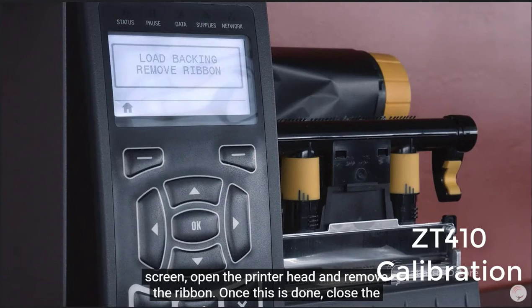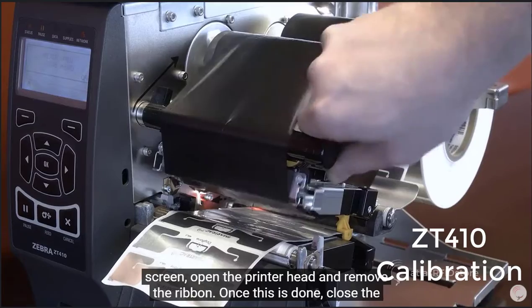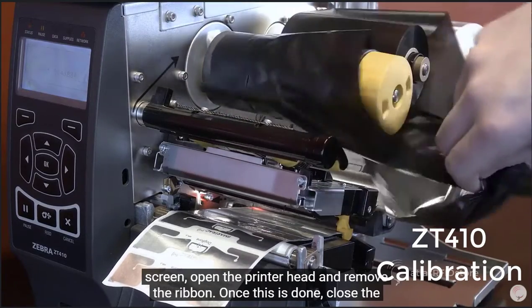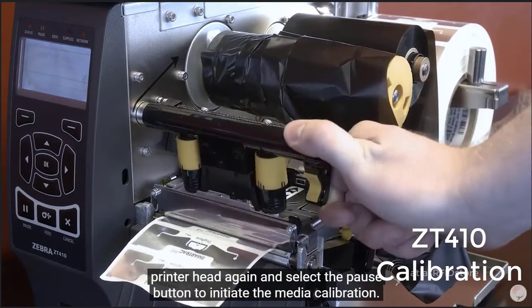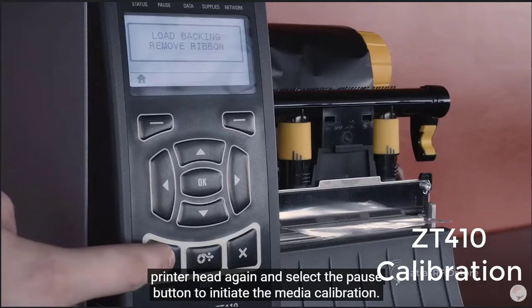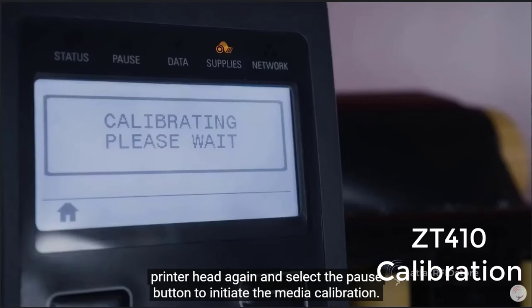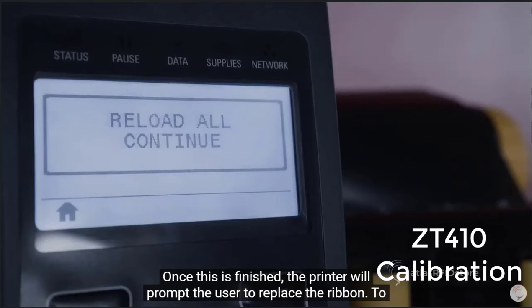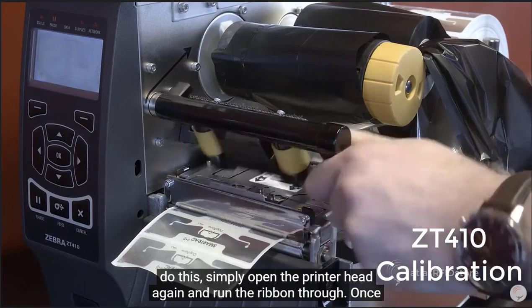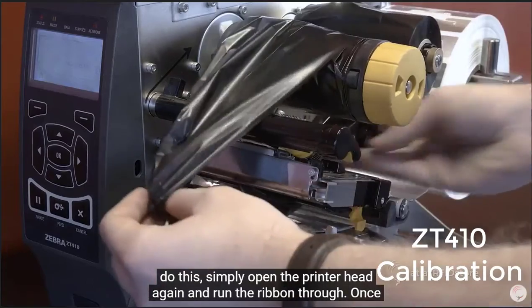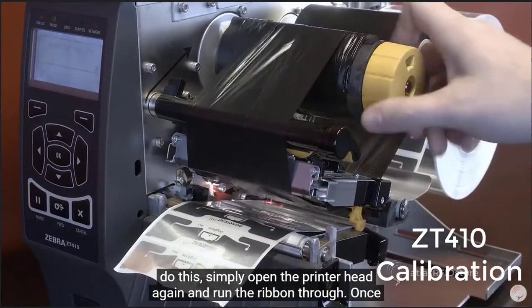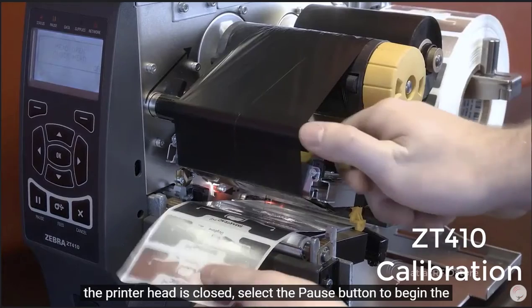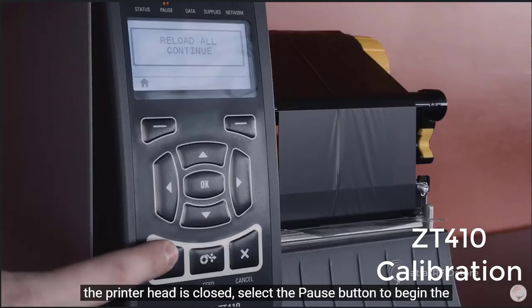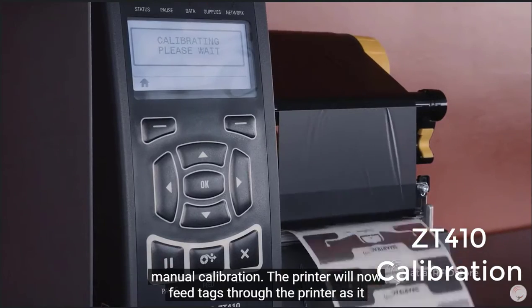Following the directions on the printer screen, open the printer head and remove the ribbon. Once this is done, close the printer head again and select the Pause button to initiate the media calibration. Once this is finished, the printer will prompt the user to replace the ribbon. To do this, simply open the printer head again and run the ribbon through. Once the printer head is closed, select the Pause button to begin the manual calibration.